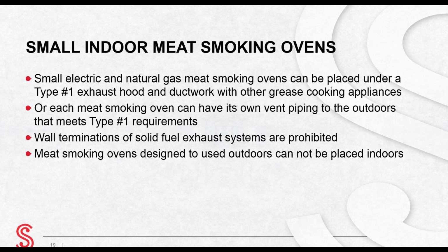Or each meat smoking oven can have its own vent piping to the outdoors that meets NFPA 96 Type 1 requirements. Wall terminations of solid fuel exhaust systems are prohibited. No ductwork is permitted through the walls, only to the roof. Meat smoking ovens designed to be used outdoors cannot be placed indoors.